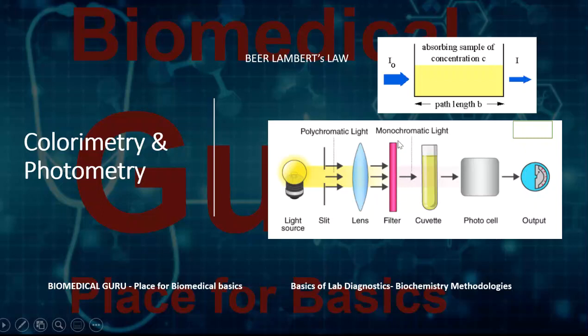Then comes a filter. What the filter does is absorb all the other colors and let only one color of light pass through. Then comes the cuvette. The cuvette is the place where the actual analyte will be, and after that there will be a measuring mechanism which will analyze the quantity of light that is falling on it. Here the quantity of light that comes here is directly proportional to the concentration of color in the cuvette.